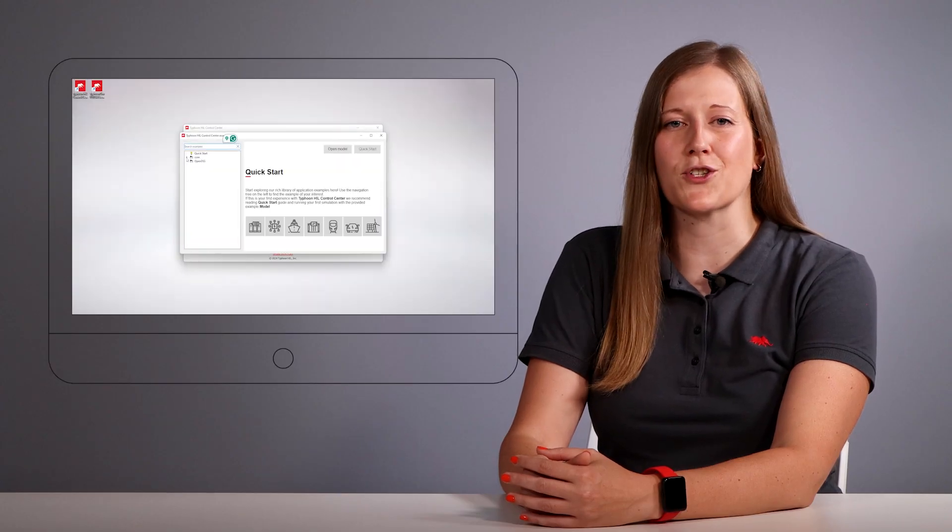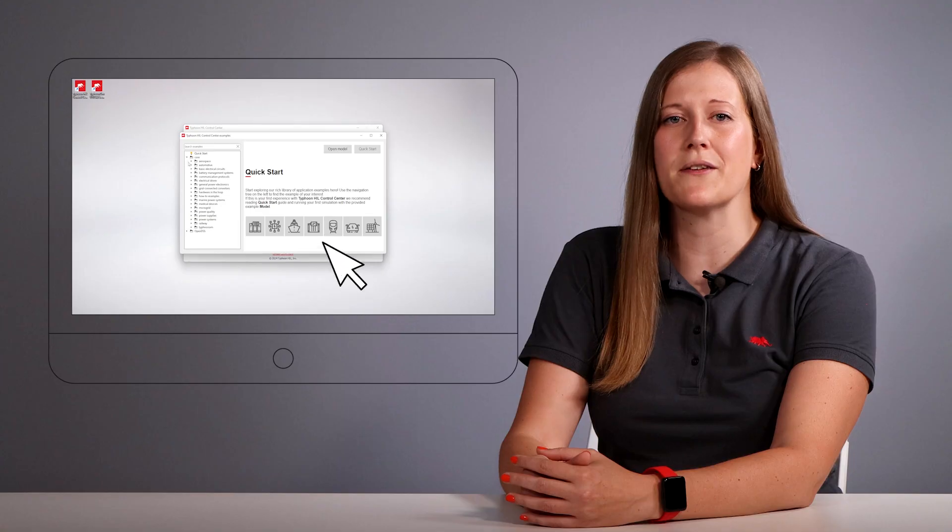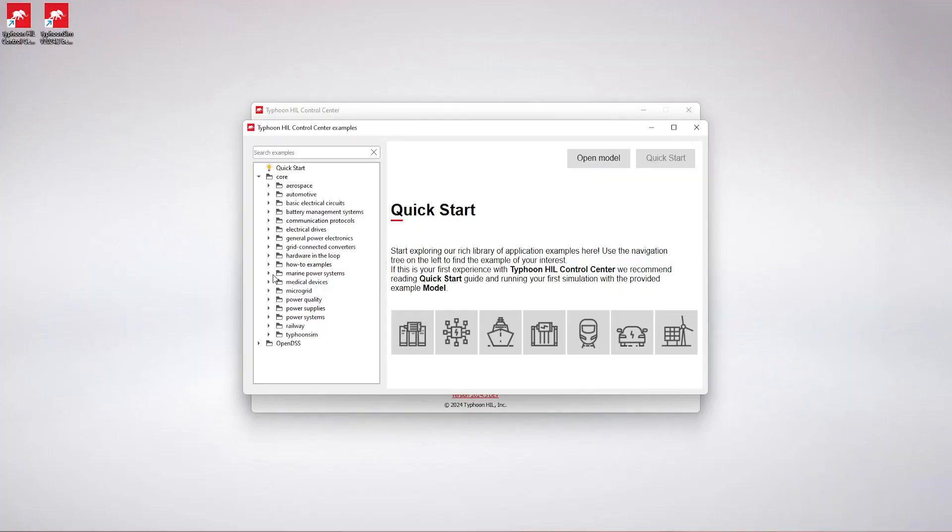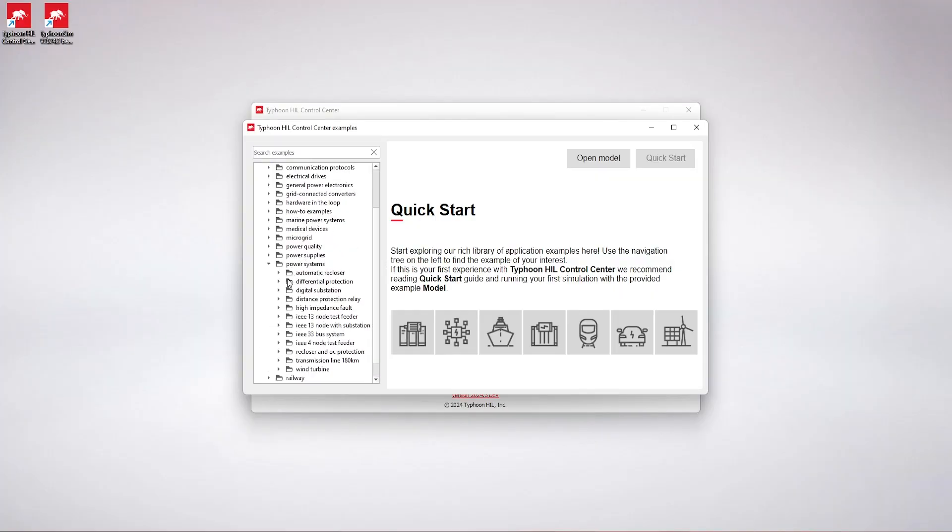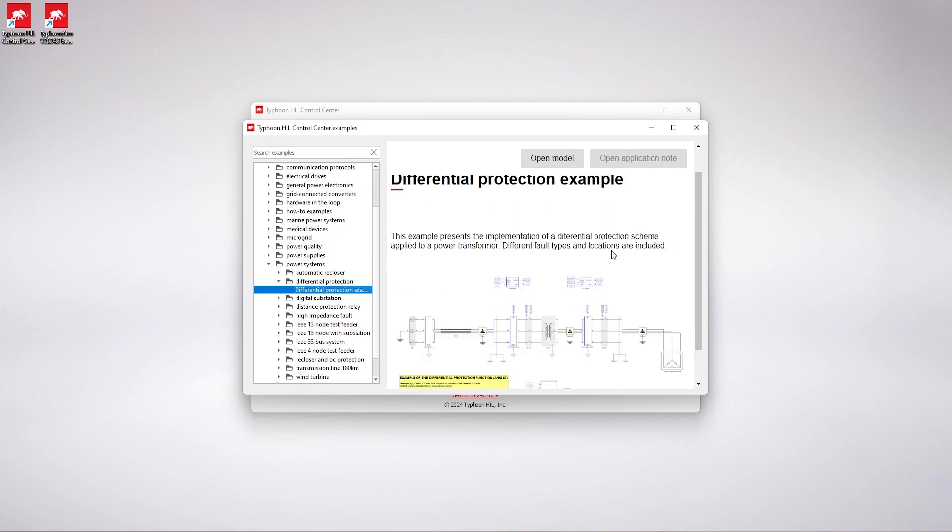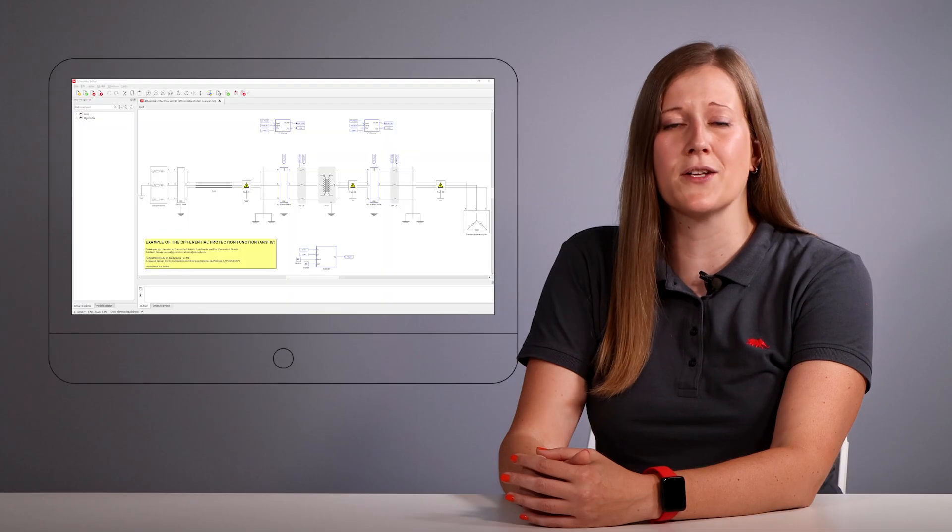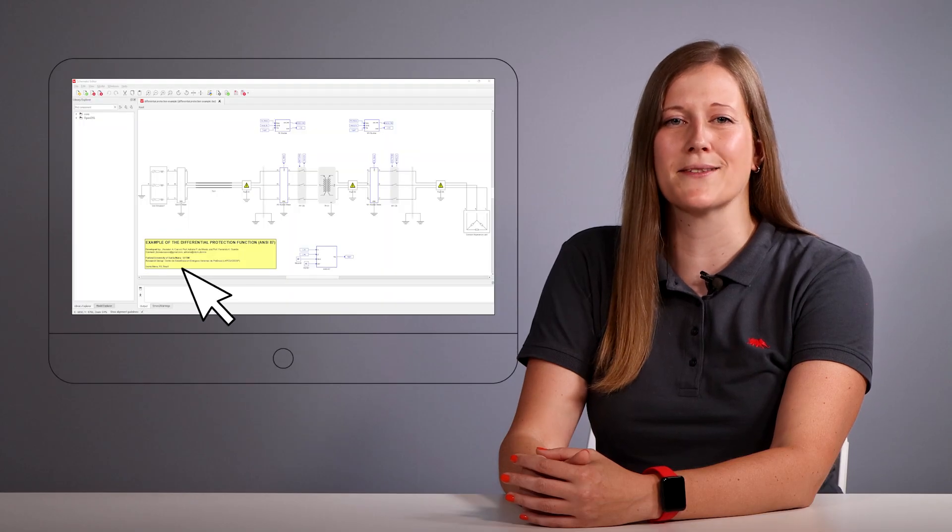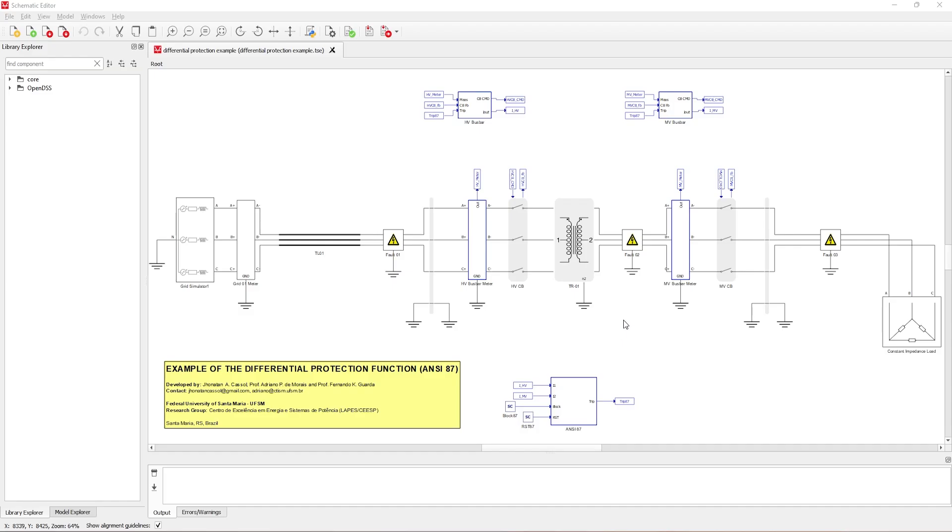We conclude with an example of differential protection, commonly referred to as ANSI 87. It demonstrates the implementation of a percentage differential protection function with an unrestrained element. This example was developed by the Santa Maria Technical and Industrial School of the Federal University of Santa Maria.